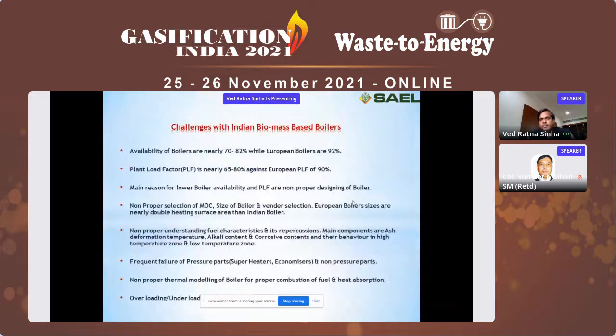There are challenges with Indian biomass-based boilers. Availability of Indian boilers is nearly in the range of 70 to 80%, while European boilers are around 92%. This is mainly due to lack of the right technology usage for the right biomass. Power plant load factor (PLF) is nearly 65 to 80% against the European PLF of 90%. The main reasons for low boiler availability and PLF are improper boiler design, improper selection of material of construction, boiler sizing, and vendor selection. European boiler sizes have nearly double the heating surface area compared to Indian boilers.